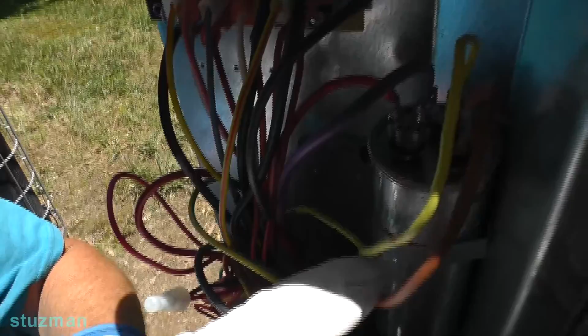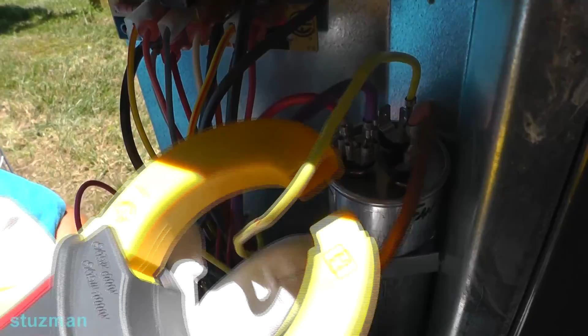Okay, I've already turned the circuit breaker back on. I went back inside. I turned on the thermostat to cool. You can see the unit is running now. And now what we're going to do is get an amp clamp set for AC amps. Now, we're going to check both capacitors here. So we're looking at the one for the compressor and also the one for the condenser fan. Now, the yellow wire is going down to the compressor. So that's for the start winding. So what we're going to do is get an amp reading on that.